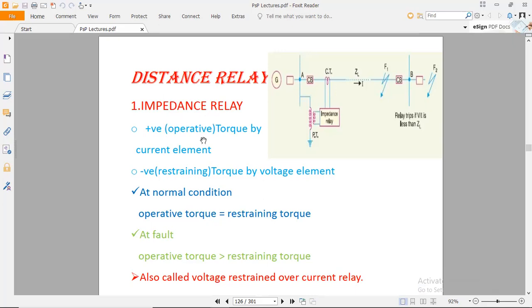Impedance relay: the positive operative torque is by the current element, and the negative restraining torque is by the voltage element. At normal condition, operative torque equals restraining torque. At a fault, the operative torque is greater than the restraining torque. It is also called a voltage restraint overcurrent relay.